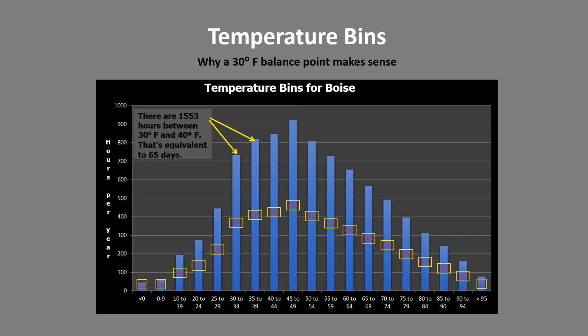We hear a lot, why do we care so much about a balance point of 30? Why don't we make it 40 degrees? What this chart does here is it breaks the temperature in Boise, Idaho into 5-degree temperature bins. So this one right here is 40 to 45, this one is 45 to 49. What's really interesting is that there are 1,553 hours between 30 and 40 degrees in Boise every winter. That's equivalent to 65 days. So you'd be telling your customers, if you had a balance point of 40 rather than 30, that you're going to have to use your auxiliary heat 65 full days more than if you had a 30-degree balance point.